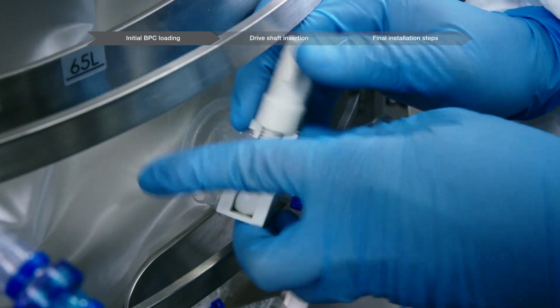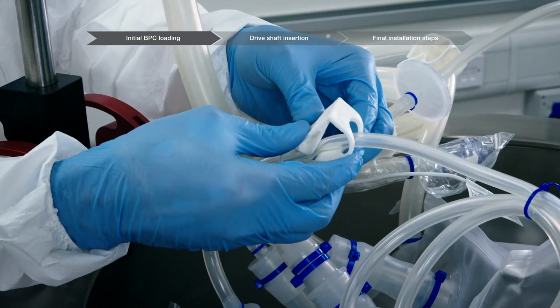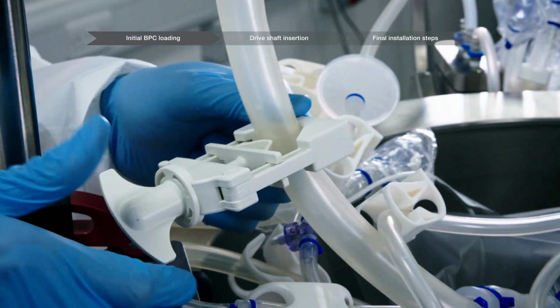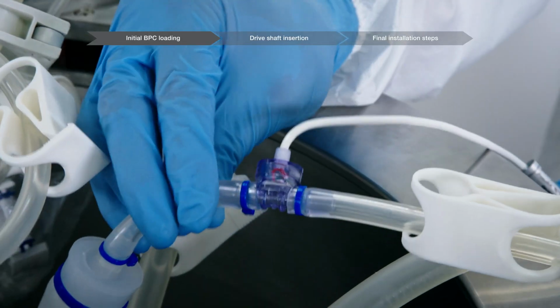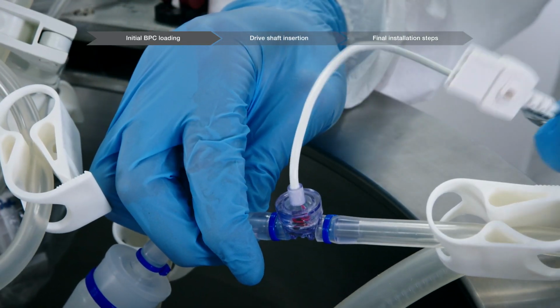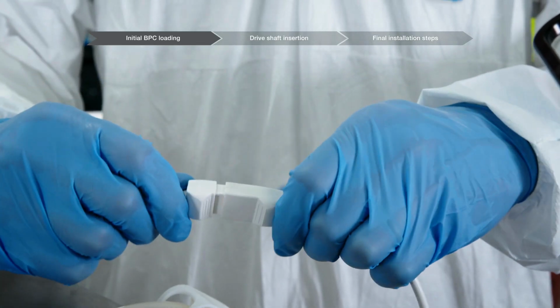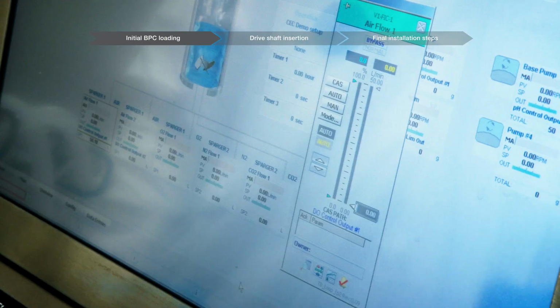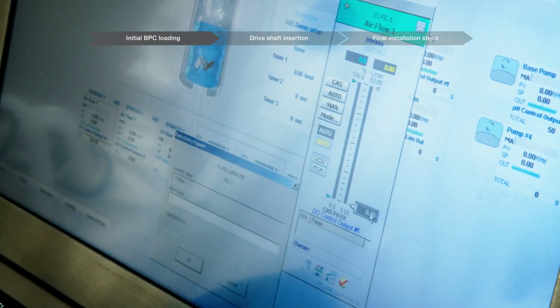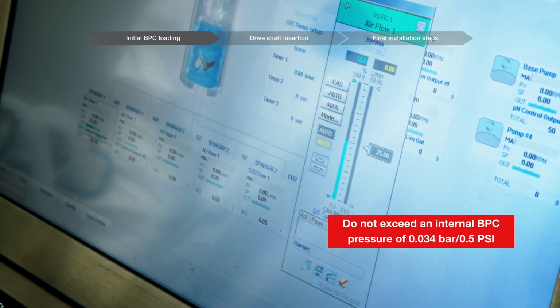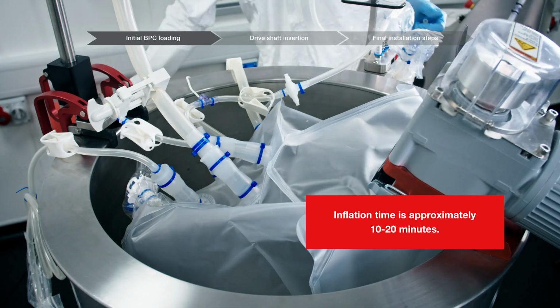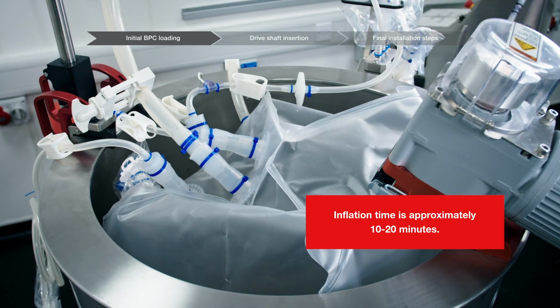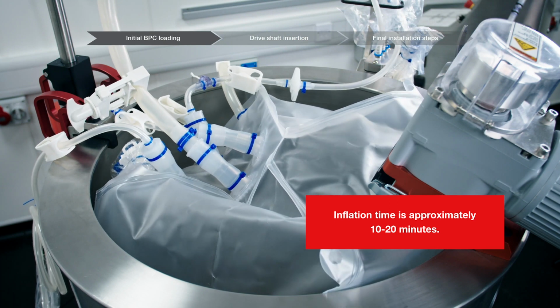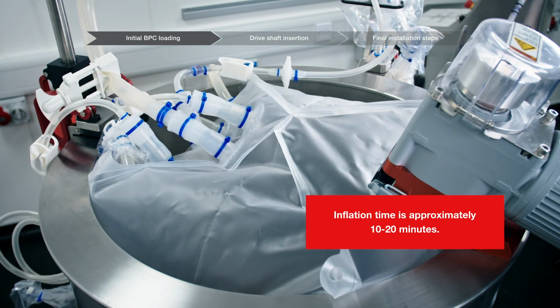Clamp off all lines prior to inflation, but leave one exhaust line unclamped. If you are using a pressure sensor to monitor inflation, connect its pressure transducer cable to the third-party controller. Inflate the BPC with air through the overlay filter, but do not exceed an internal BPC pressure of 0.034 bar or 0.5 pounds per square inch. Inflation time is approximately 10 to 20 minutes. Time will vary based on flow rate, inlet pressure, and container volume.